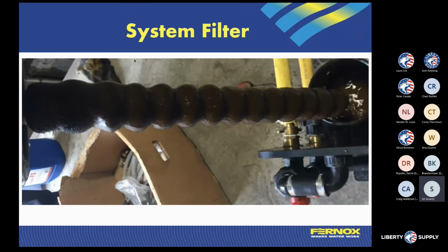And as I pull that sediment through, we're going to be collecting that iron oxide. So this is going to do another step of removing that item. So what you're looking at here is a filter after it's gone through the system and we flushed it all out. This is what we grabbed in that filter system while we're doing a power flush.